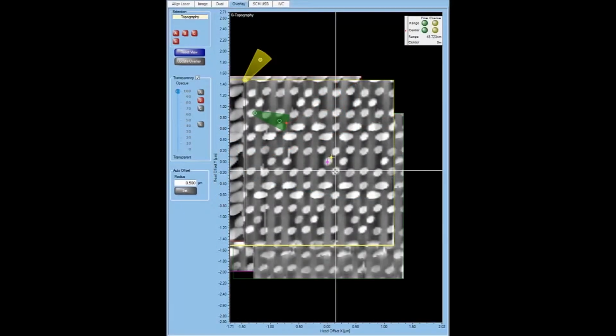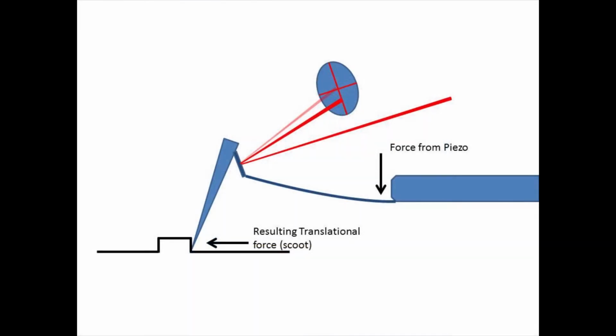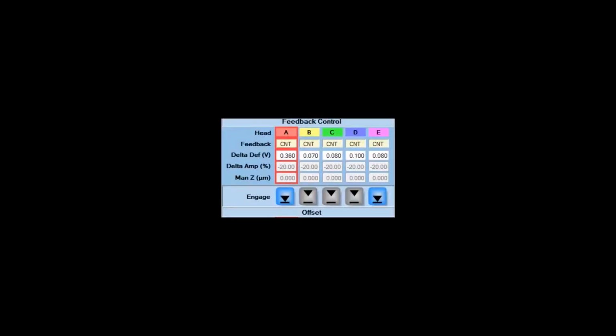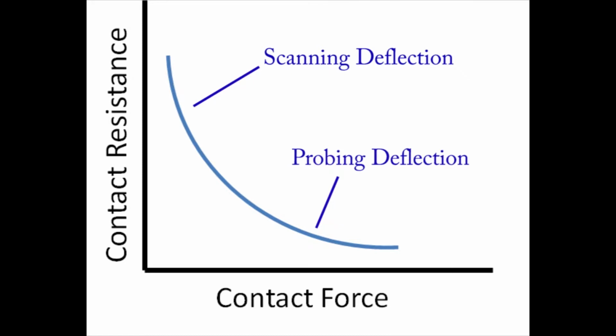Place the probe tip behind the contact with respect to the chosen head's position. By increasing the delta deflection, the probe tip will scoot into the side of the contact. Increasing the deflection further will cause the pressure between the tip and contact to increase, lowering the contact resistance.